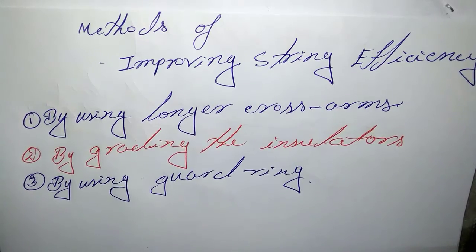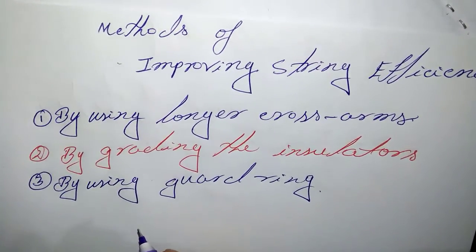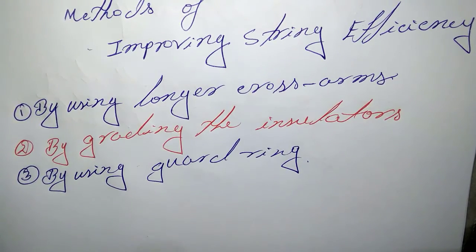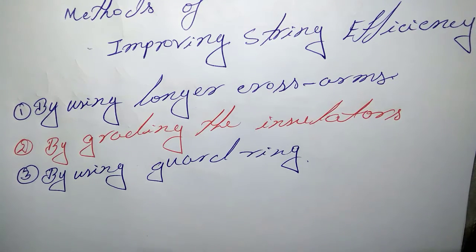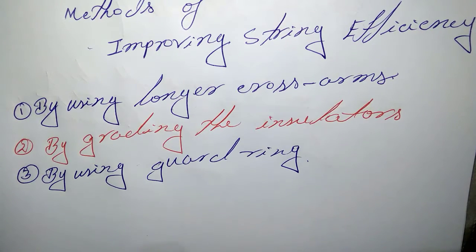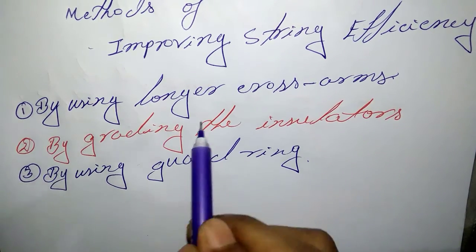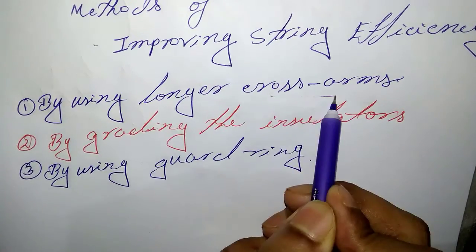The voltage decreases progressively as the cross arm is approached. If the insulation of the highest stressed insulator breaks down, or flashover takes place, the breakdown of other units will take place in succession.